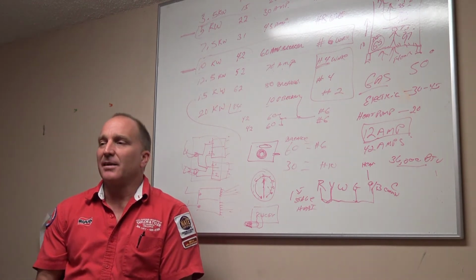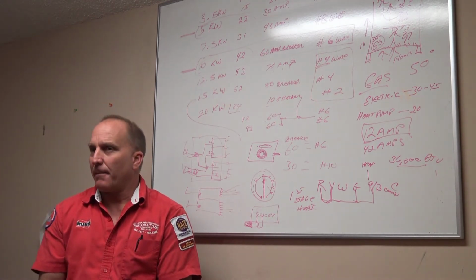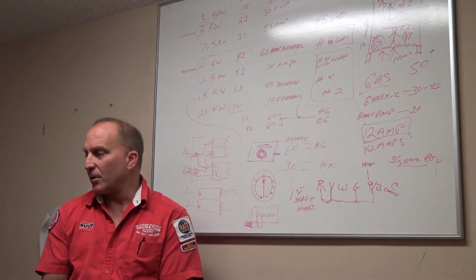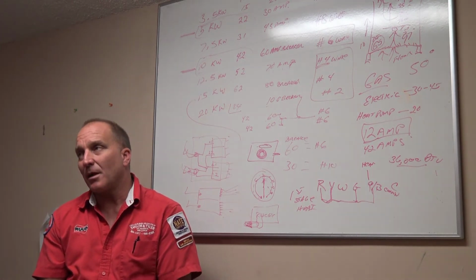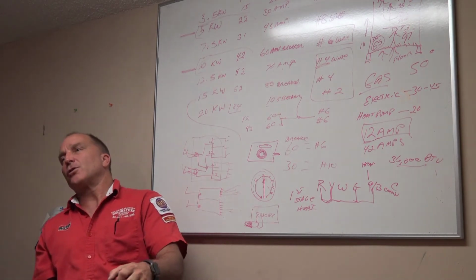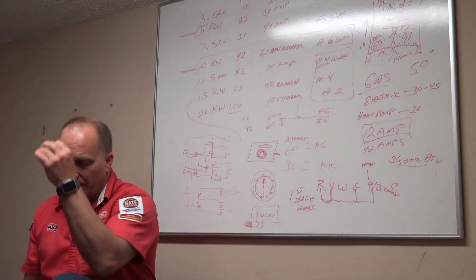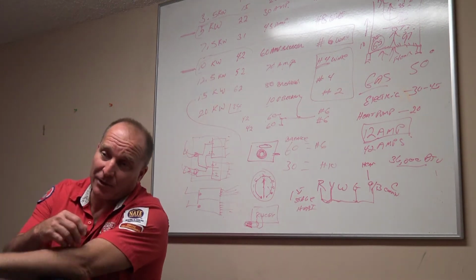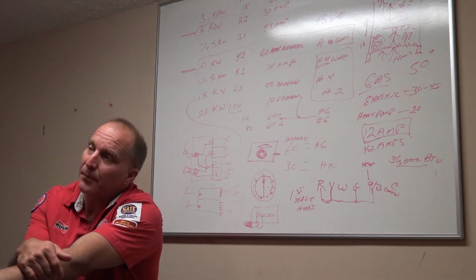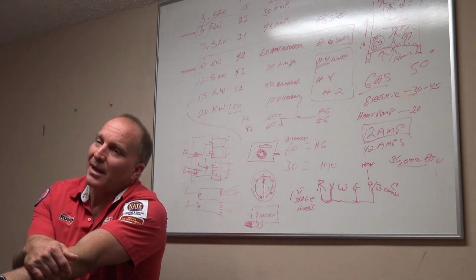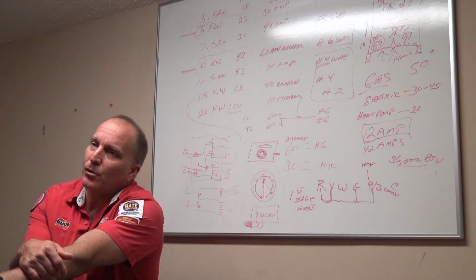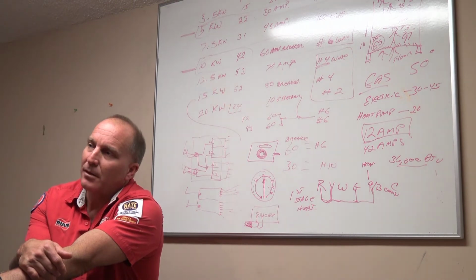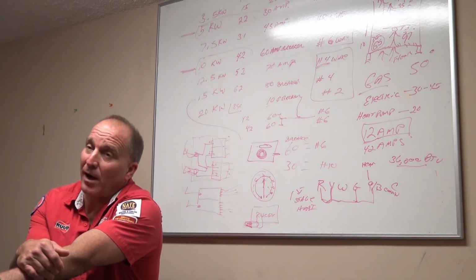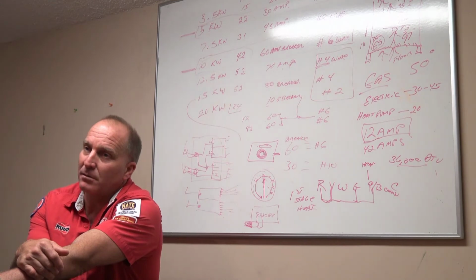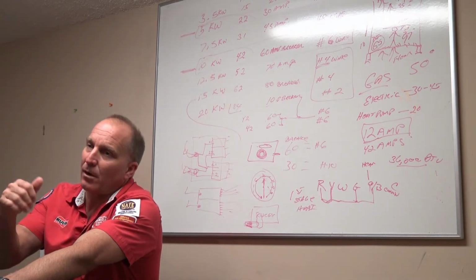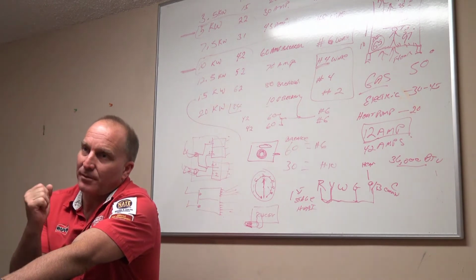If you have a bad disconnect, like that disconnect I just showed you over there, I'm going to tell you something: if you do not do this, you will go back out to these customers' houses again very soon if you do not do what I'm fixing to tell you to do. That disconnect box for that electric air handler right there that we showed was burned up. I am telling you to go to the main electrical panel. Take the cover off the main electrical panel, find the breaker for that particular furnace, and then turn the breaker off and tighten the wires on that breaker too.